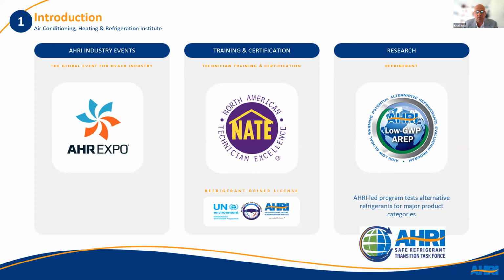Another area is refrigerant, which is a big item certainly when it comes to climate change. AHRI has a safe refrigerant transition task force formed to address every step of the supply chain in the safe transition to low global warming potential refrigerants. In addition, AHRI Standard 700 specifies purity specifications for refrigerants, to verify composition and specify associated methods of testing, whether the refrigerants are new, reclaimed, or repackaged. Standard 700 in particular is being adopted by several regulatory bodies and institutional clients worldwide.